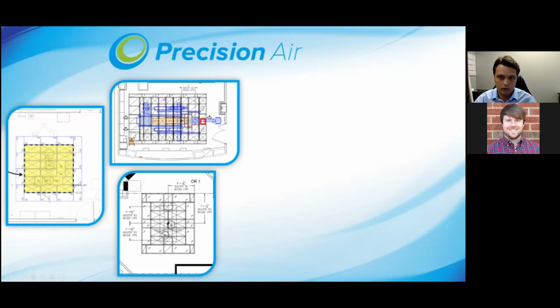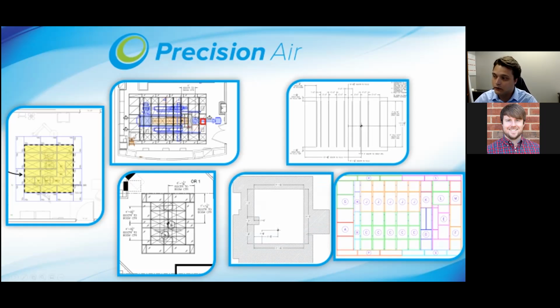As a result, we need to coordinate everything into one large system that satisfies all the requirements in that ceiling. We provide drawings that show not just the air, but where everything else lands—documenting boom locations relative to isocenter and all other equipment relative to each other. We also provide drawings showing where the structural elements go, such as ceiling-level unistrut, where plans will go, what the rough ceiling opening is, and a map of how that puzzle fits together with all the modular subsections going into the ceiling.